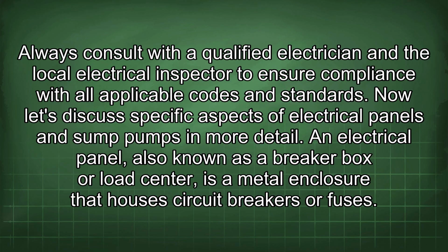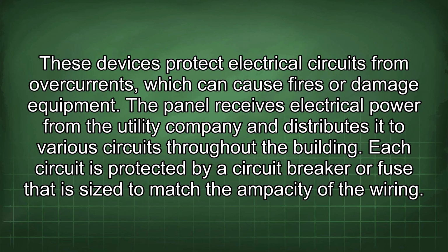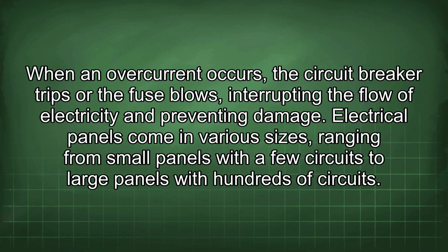An electrical panel, also known as a breaker box or load center, is a metal enclosure that houses circuit breakers or fuses. These devices protect electrical circuits from overcurrents, which can cause fires or damage equipment. The panel receives electrical power from the utility company and distributes it to various circuits throughout the building. Each circuit is protected by a circuit breaker or fuse that is sized to match the ampacity of the wiring. When an overcurrent occurs, the circuit breaker trips or the fuse blows, interrupting the flow of electricity and preventing damage.